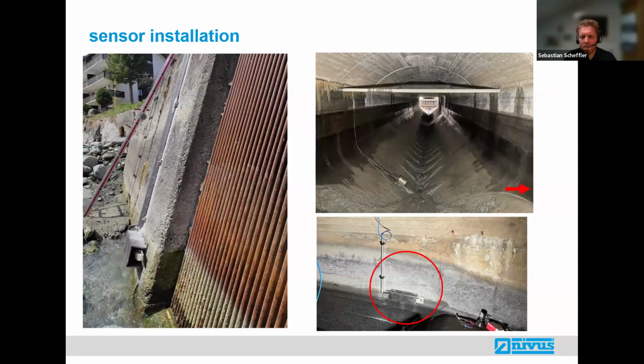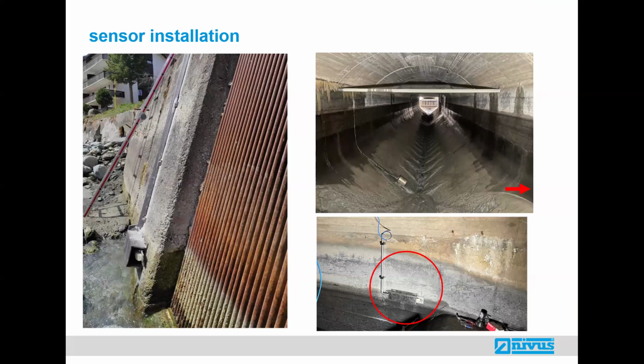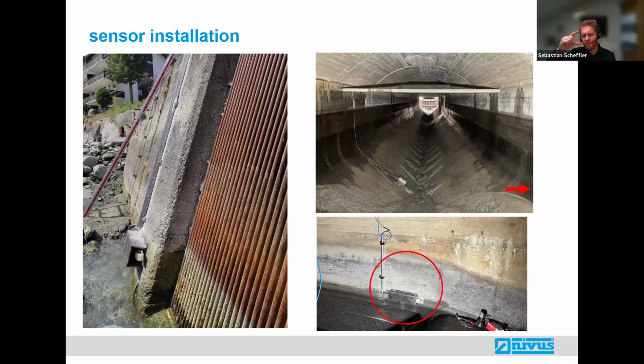So you mean the sensor looking up, or looking down? That's what was being asked, whether it could be installed vertically or not. It is possible, but if you install it looking down or looking up, you just have to be sure that you have a distance to the top of the water, to the water level, or to the bottom, of at least 15 centimeters for the measurement. And then again, you have to find a way to protect the sensor from debris or boulders. So I think the recommended way is to have the sensors facing downstream.